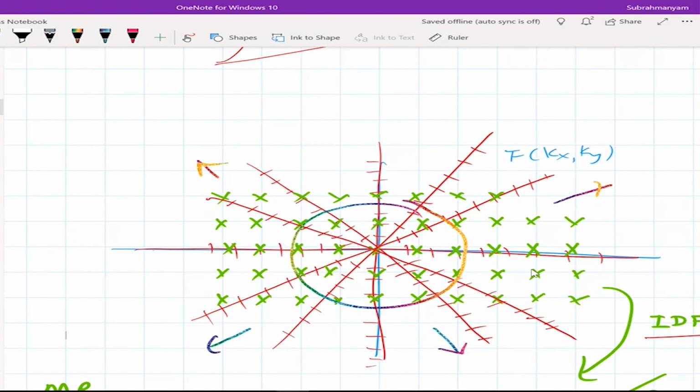On the contrary, there are a lot of MR acquisition techniques where they acquire the signal in kx ky space on a regular grid. In that case, the Fourier slice theorem is good enough. They do the reconstruction with simply the Fourier slice theorem, unless they are taking samples in a different way, in which case they would borrow or adapt methods coming from CT image reconstruction.